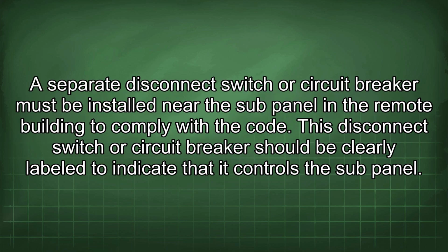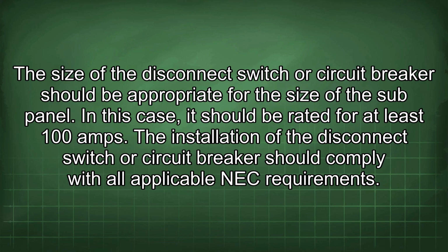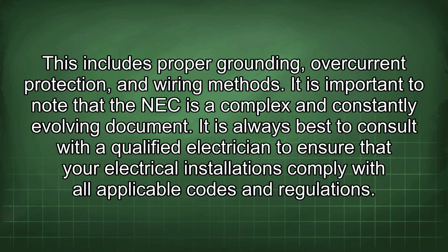A separate disconnect switch or circuit breaker must be installed near the sub-panel in the remote building to comply with the code. This disconnect switch or circuit breaker should be clearly labeled to indicate that it controls the sub-panel. The size of the disconnect switch or circuit breaker should be appropriate for the size of the sub-panel. In this case, it should be rated for at least 100 amps. The installation should comply with all applicable NEC requirements. This includes proper grounding, overcurrent protection, and wiring methods.